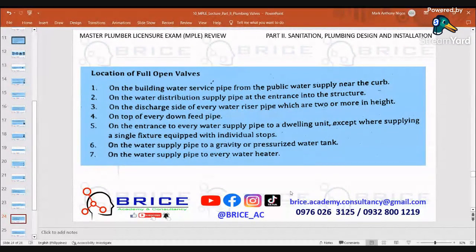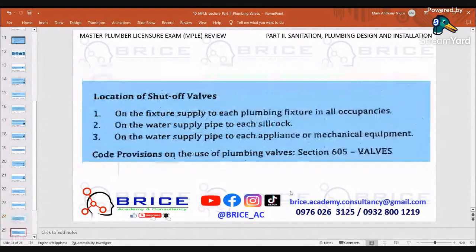Number 5, on the entrance to every water supply pipe to a dwelling unit, except for supplying a single fixture equipped with individual stops. Number 6, on the water supply pipe to a gravity or pressurized water tank. Number 7, on the water supply pipe to every water heater.